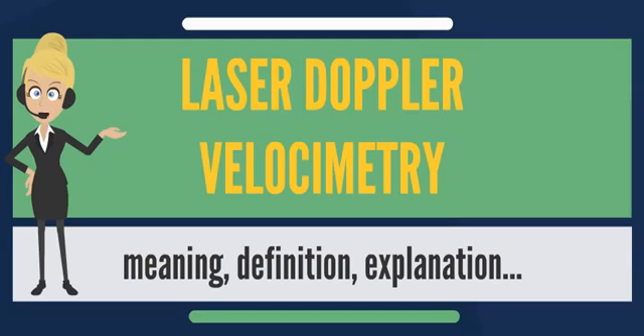Particles passing through this volume will scatter light from the measurement beam with a Doppler shift. A portion of this light is collected by the receiving optics and transferred to the photodetector. The reference beam is also sent to the photodetector, where optical heterodyne detection produces an electrical signal proportional to the Doppler shift, by which the particle velocity component perpendicular to the plane of the beams can be determined.